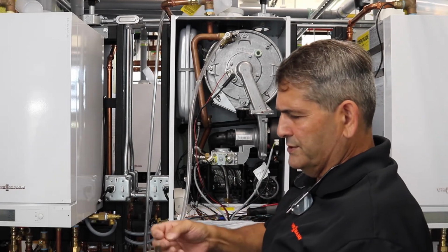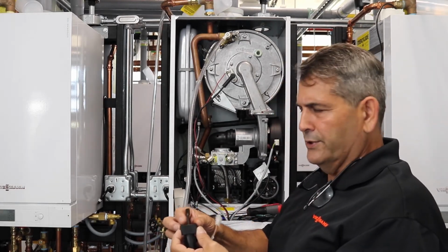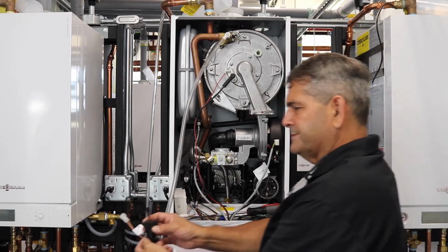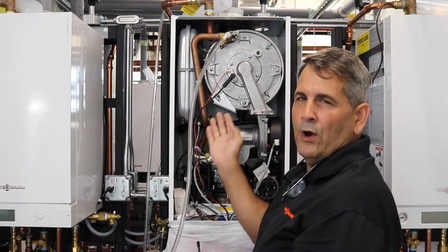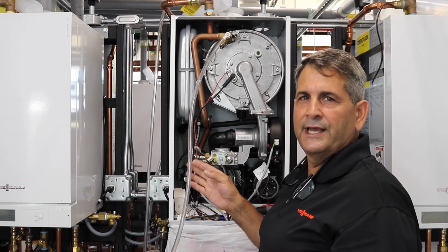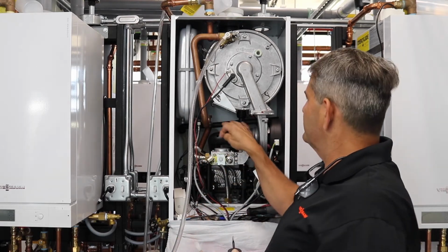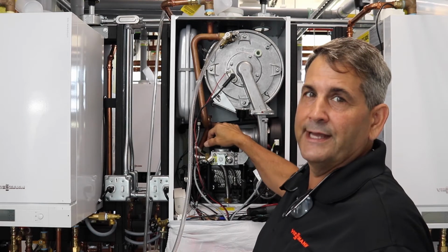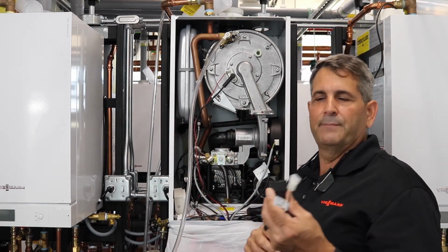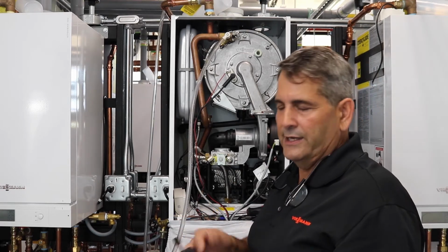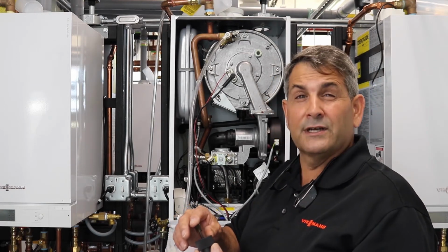So I check to make sure there's no buildup on there. Take a look at it and see how it's done. Also, you might want to open up a valve, push some water out of there, or purge it again, and make sure that there's no debris or sediment down in the bottom of the pipe where this can touch or rub and keep it in a stuck position. And like I said, I have seen it with solder balls stuck underneath it.